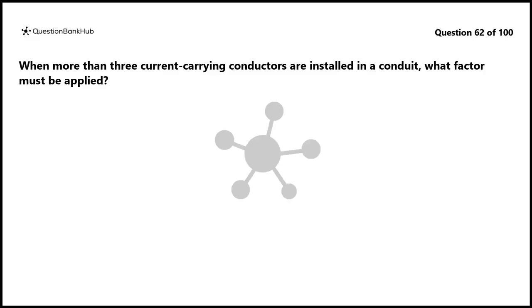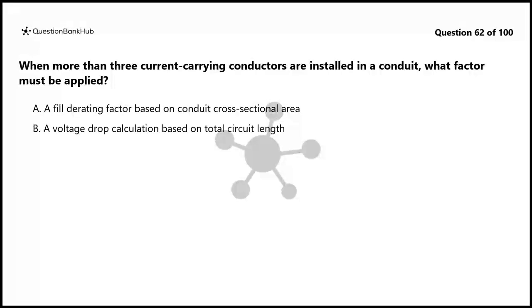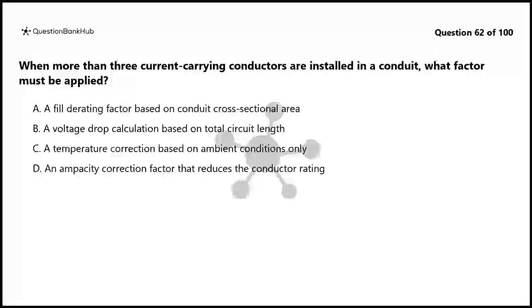Question 62. When more than 3 current-carrying conductors are installed in a conduit, what factor must be applied? A. A fill derating factor based on conduit cross-sectional area. B. A voltage drop calculation based on total circuit length. C. A temperature correction based on ambient conditions only. D. An ampacity correction factor that reduces the conductor rating.